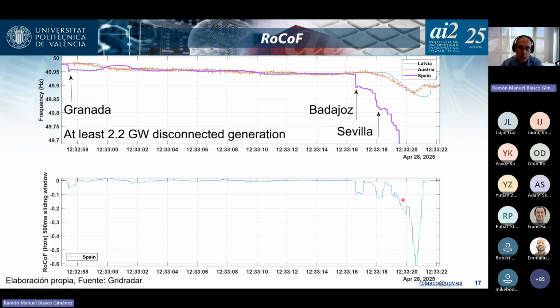I must say that some colleagues who have PV plants have a PV plant setting of 0.3 hertz per second for RoCoF, and they tripped on RoCoF. The point is that those PV plants were commissioned a long time ago, and they were okay and certified at the time. But since then, the regulations have changed, and the protections were set at the RoCoF level, correct legally, but too low in that case.